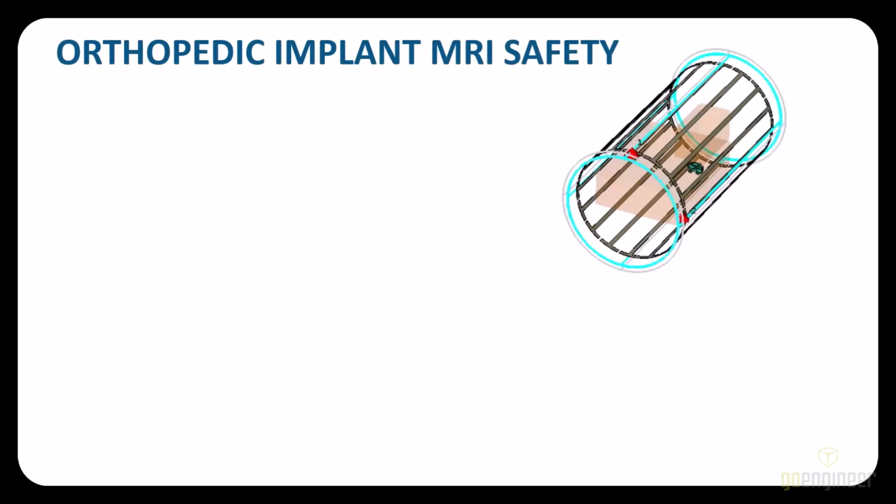What happens in cases where the patients have metallic implants of some kind and have to undergo a scan? How do we assess the safety in these scenarios? For this, we have the ASTM standards that specify process and metrics required to evaluate passive and active implant safety in MRIs. The standard for passive implant safety requires a phantom shaped like a brick to be utilized in place of the human body. This phantom would be filled with a saline gel that imitates the tissues inside the body, while the implant is placed 2 centimeters away from the edge of the phantom.